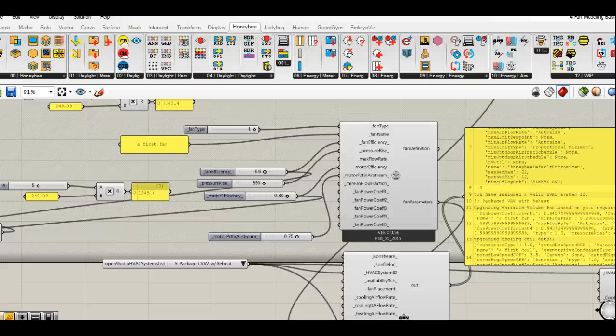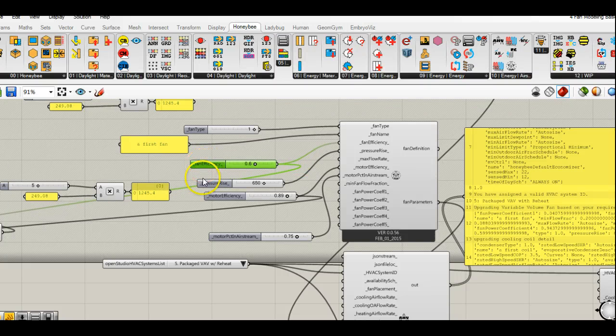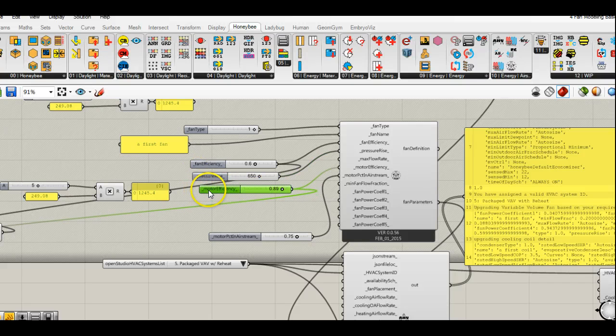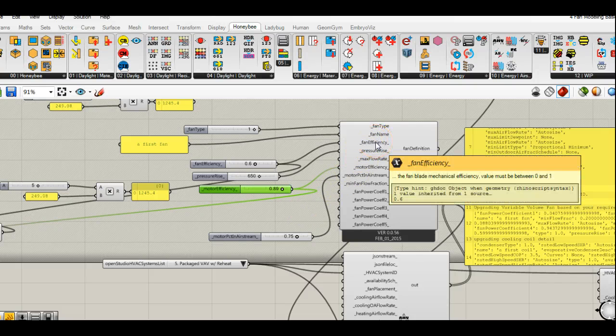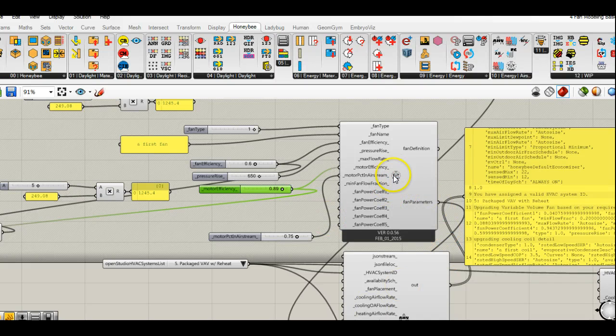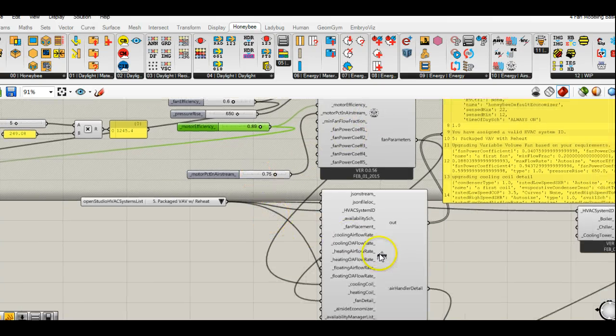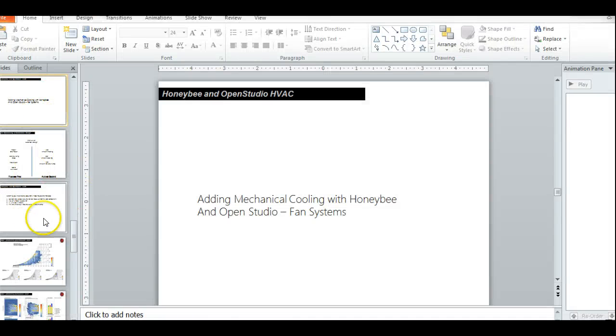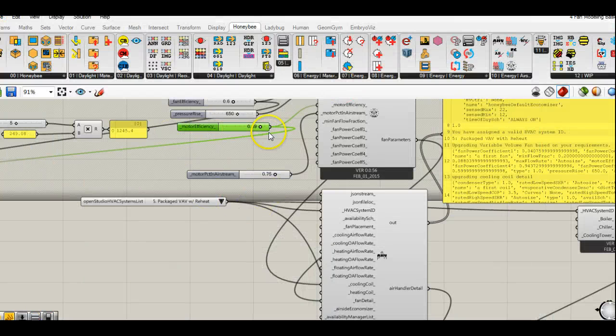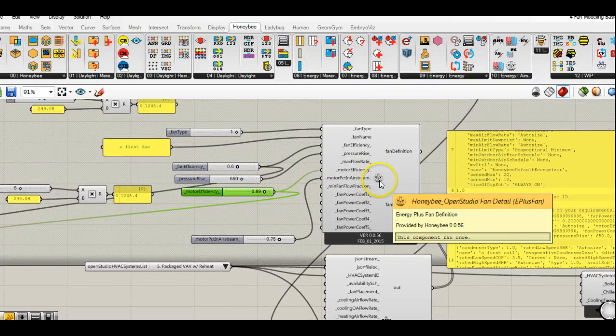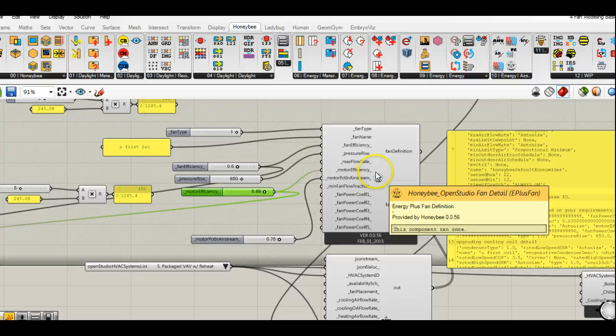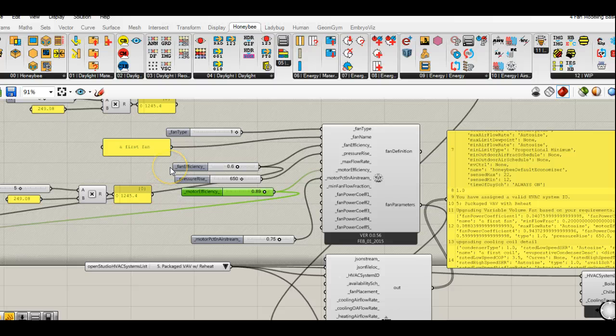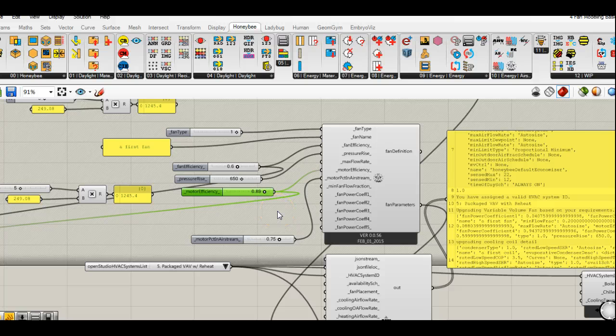There's some nuances you're going to want to think about from an energy modeling and LEED perspective. In OpenStudio, when you specify a fan and attach it to an air handler, you're only specifying one fan. In a real system, a lot of times there will be a supply fan and a return fan, and there might even be some exhaust fans. That's a little bit more advanced, but the point is when you say fan, a lot of times you mean both supply and return.